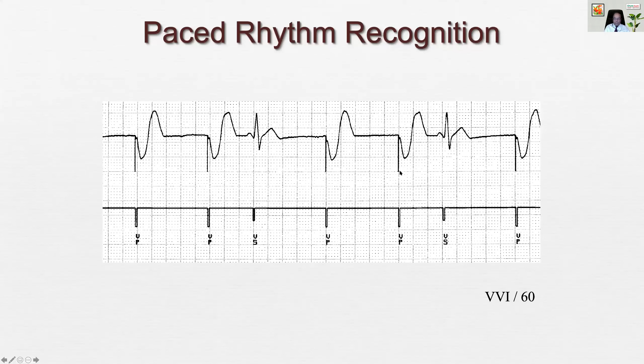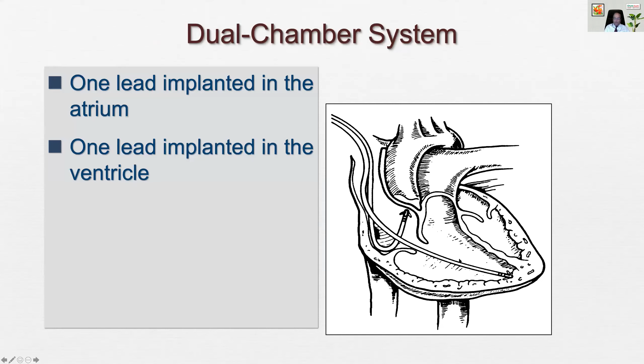A dual chamber pacemaker system has two leads, one implanted in the atrium, as we can see in this picture on the right side, and one lead in the ventricle. So it's a dual chamber system, and they can function in one of four ways. So you can have atrial sensing, ventricular pacing, that is in the top strip. You can have atrial pacing and ventricular pacing, so both chambers are pacing, in the second strip. In the third, we have atrial pacing but ventricular sensing, because the AV conduction in this example seems to be intact. And in the fourth, the pacemaker is in standby. There are many patients who have an intermittent problem. So, for those, they may have either sinus pauses or intermittent complete heart block.